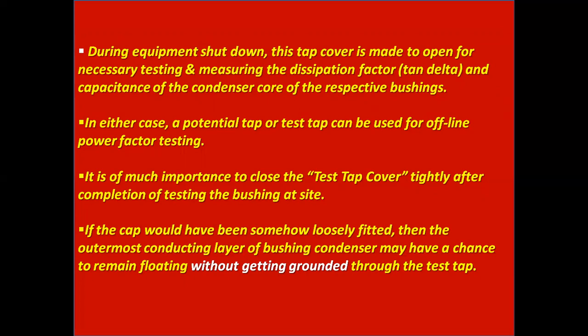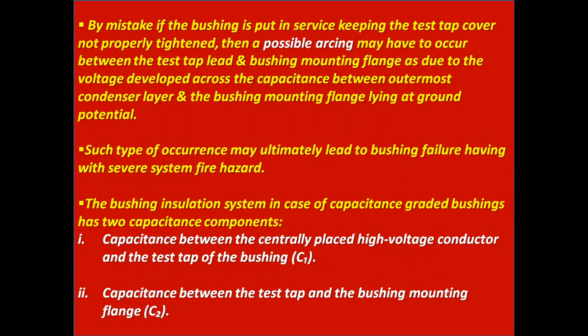If the cap is somehow loosely fitted, then the outermost conducting layer of the bushing condenser may remain floating without getting grounded through the test tap. By mistake, if the bushing is put in service with the test tap cover not properly tightened, then arcing may occur between the test tap lead and the bushing mounting flange, due to the voltage developed across the capacitance between the outermost condenser layer and the bushing mounting flange lying at ground potential. Such an occurrence may ultimately lead to bushing failure with a severe system fire hazard.